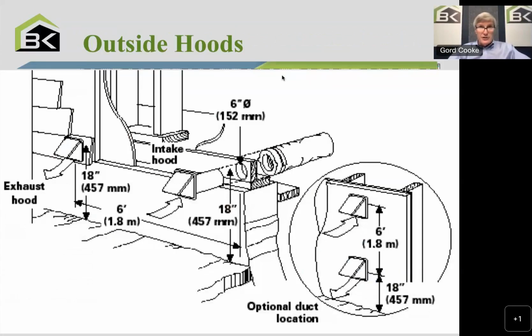Typically, the hoods are installed about 6 feet apart. They have to be a minimum 3 feet apart, unless you're using one of those concentric hoods. Typically, they need to be above snow levels, so typically at least 18 inches above grade. In some communities, it might need to be more than that, depending on where you are in the snow areas. So this is typically where they're at. And if they're too low to the ground, you should look to see if there's a way to change that.